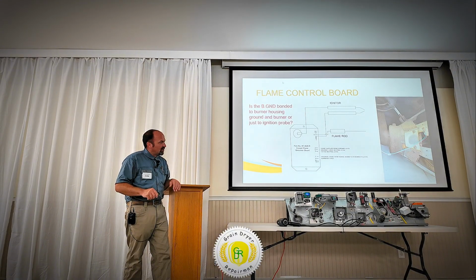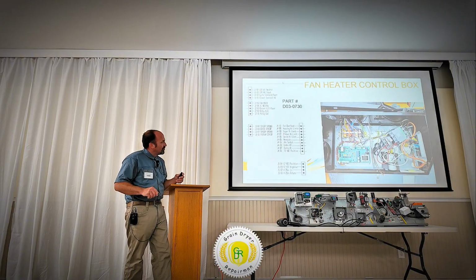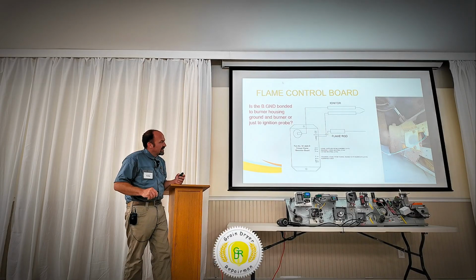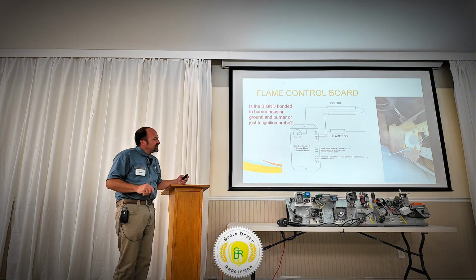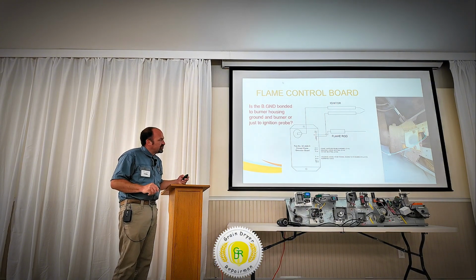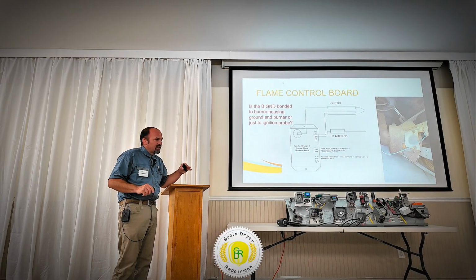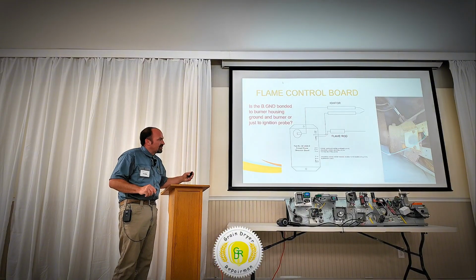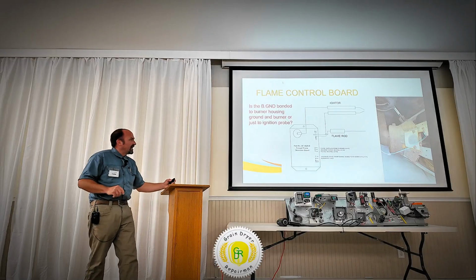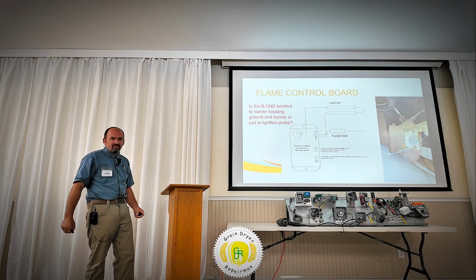This has a ground wire going to the burner here, and that goes back and gets connected to a ground bar in the electrical box right here. That wire goes over and down to here. This B ground needs to be connected to that ground terminal, because this board is sensing between these two terminals for its flame sensing to ground. Your flame sensing and your board longevity are all going to work better if you bond that to ground. Your B ground needs to be connected to ground. That's something that I would do going through at pre-season.